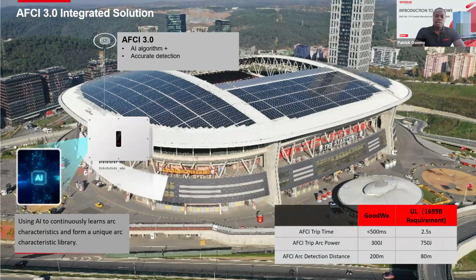Then we have the arc fault circuit interruption, AFCI. As you can see, this is a standard feature that's required in different continents like Europe and the USA. What an arc fault circuit interrupter entails is the reduction of fire hazards from your PV panels. With GoodWe, there is an international standard that is required when you're developing this AFCI, and GoodWe's protection level is even more sensitive and fast responding, to prevent any growth of arcs in your PV system. The level required is 2 seconds up to 2.5 seconds, but with GoodWe, you can get less than 500 millisecond response or trip time. We can sense arcs before they grow larger than 300 joules, and we can also sense arcs that are even 200 meters away from the inverter. This AFCI is AI operated, very accurate, and it also learns your system.